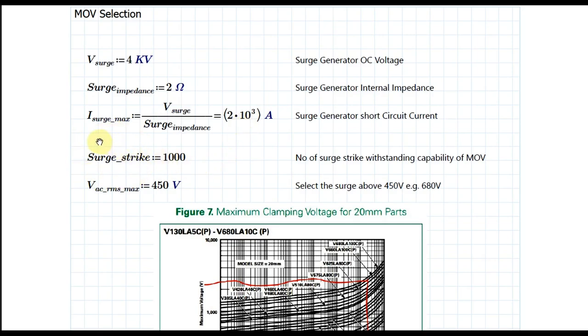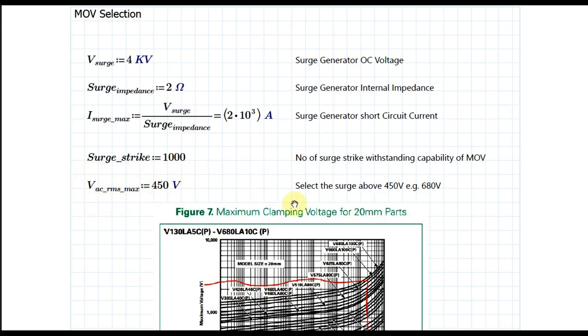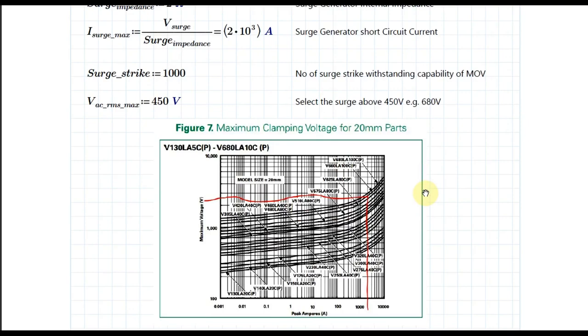Now, let's say you want to design an MOV that can withstand 1000 surge strikes. Your RMS input voltage is 450 V. You should select an MOV rated at least 1.2 times your rated RMS voltage. For 450 V RMS, you may select an MOV rated for 680 V RMS.